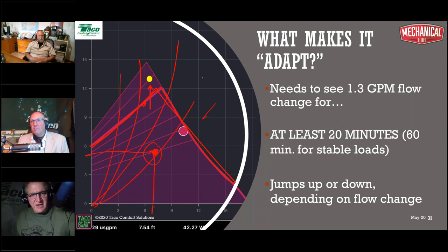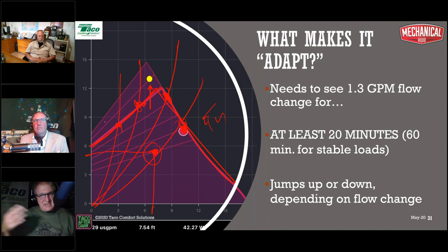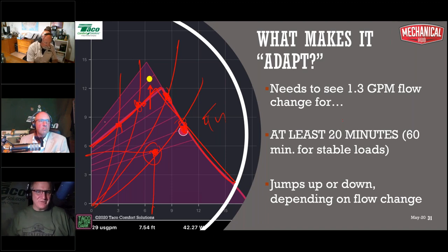It's operating here and here. That's still going to be full speed, fixed speed at 44 watts. But over here, I'm operating at a lower speed. Over here, I'm operating at a lower speed. So you're going to see the speed change and the wattage change. And you think, well, it's got to be doing what it's supposed to be doing, right? Well, it's just working on that line. And that's true of any fill-in-the-blank Adapt. That's kind of how it works. If this thing runs for a hell of a long time and you put it into some sort of mode where you have constant circulation for a long time, you may see it drop down here.